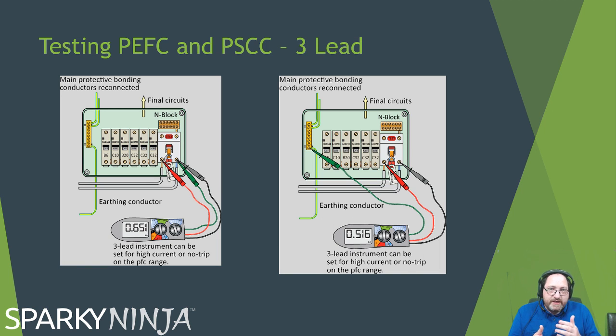Discuss it with your assessor if it's a 3 lead instrument you're being told to use. I always introduce different instruments. I bring an array of them, and I always make sure that anyone who's brought their own has an effective rig to test safely, because it's important that you test safely. But you do, with the 3 lead, have to put both the neutral and earth for PSCC, the left one here, on neutral. Okay.